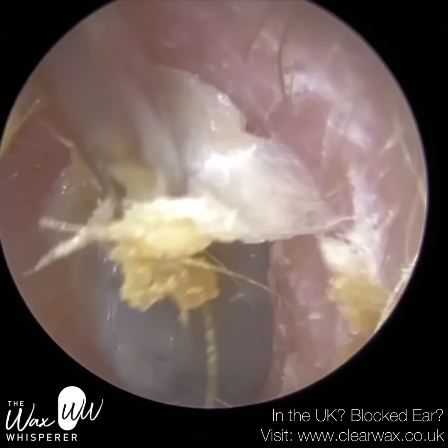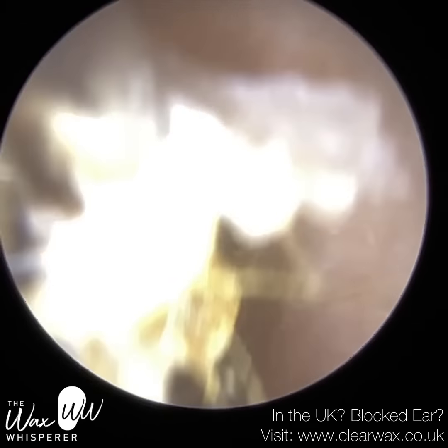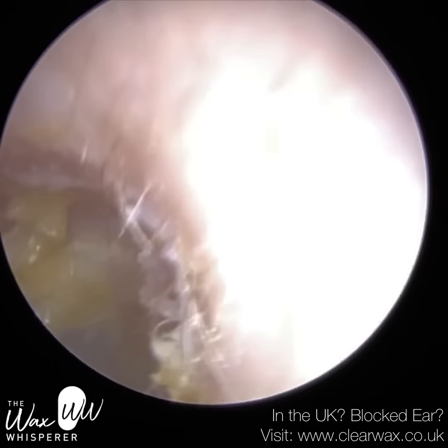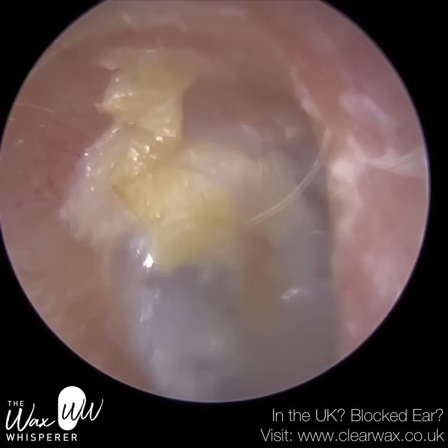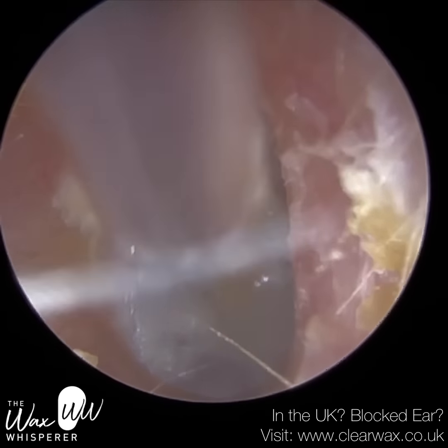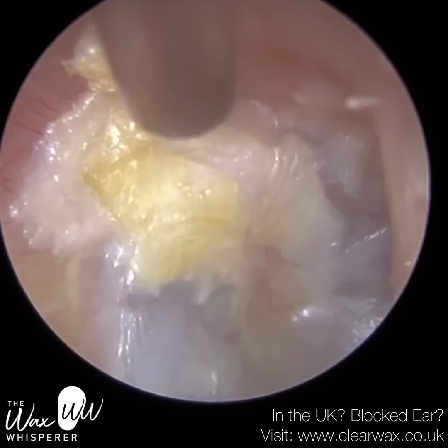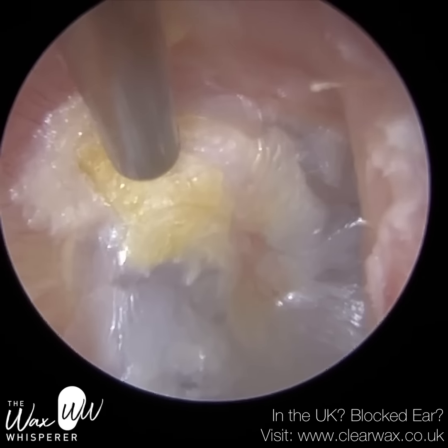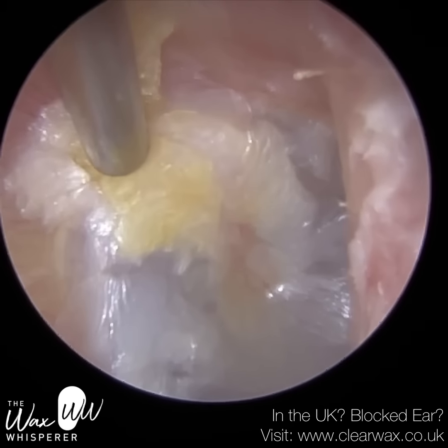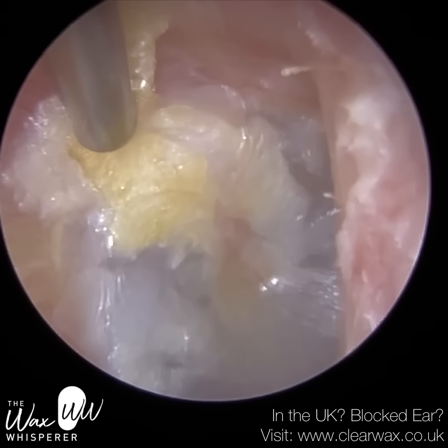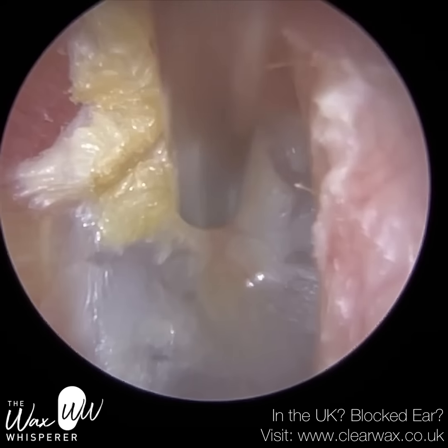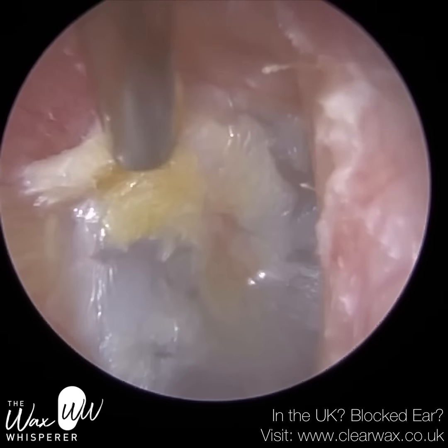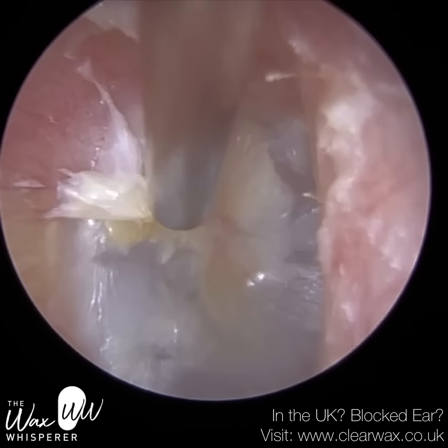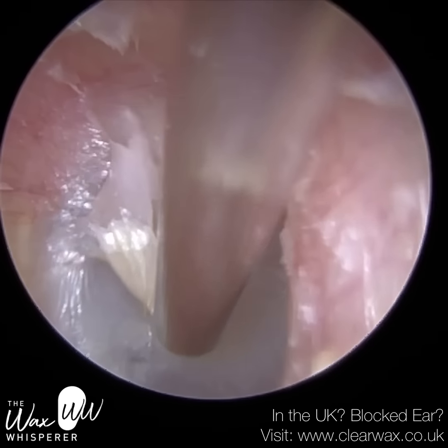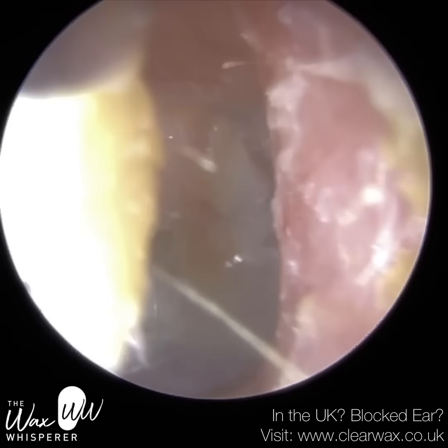The internal diameter of the fine end suction probe is about 1 millimeter. In comparison, the standard Zollner suction probe that we typically use has an internal diameter of around 1.7, so it's almost half the diameter of a standard Zollner suction probe. And when we're working on the eardrum as we are here, the fine end comes into its own. Because it's a narrower tip, it provides you more precision, accuracy, and if you do come in contact with the eardrum, it's less likely to cause any physical trauma.